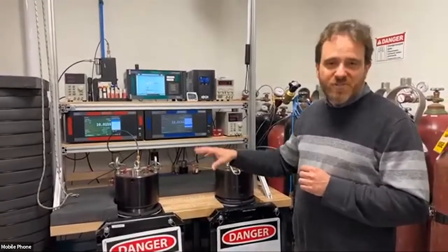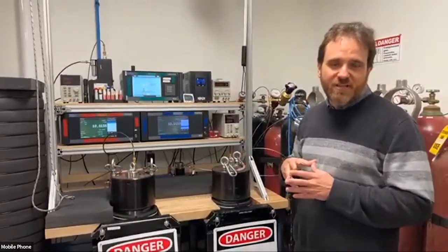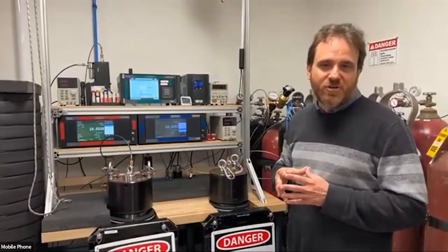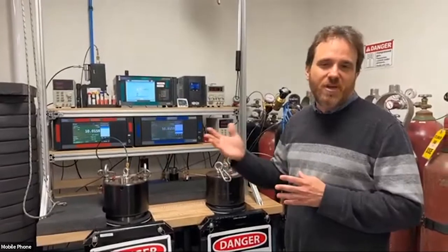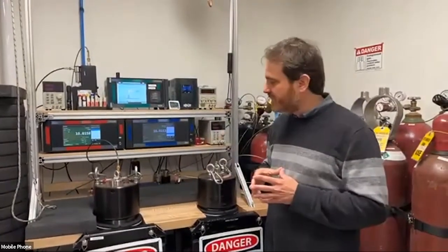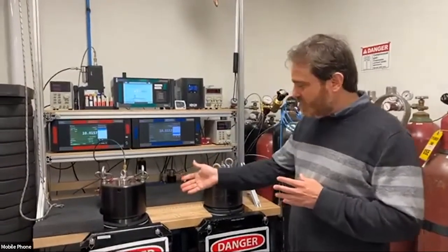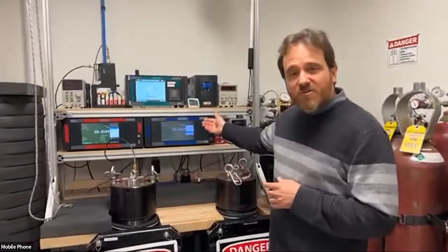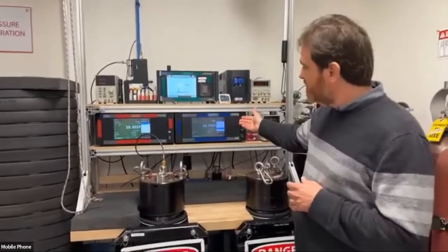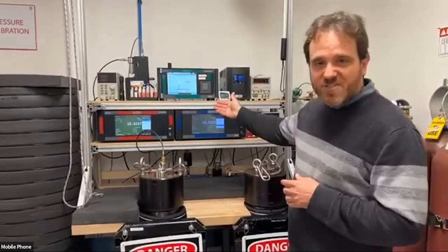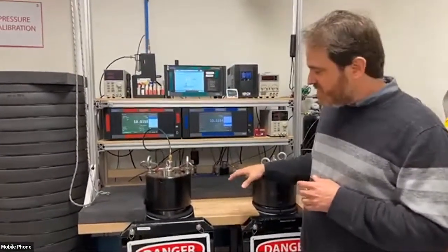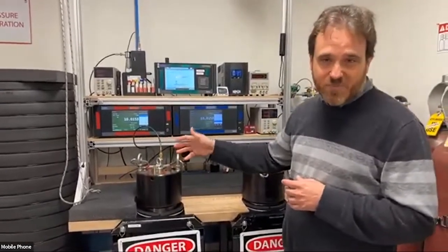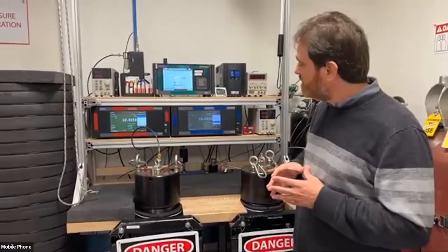The reason we do both temperatures is to calibrate the instrument to compensate for temperature dependency. So we do pressure correction off of temperature. The instruments are immersed in these tanks. In terms of the reference standards that we use, you can see 3 of our reference standards for these pressure levels. I should note that these pressure vessels can only go up to 2000 dbar, rated for that pressure level.